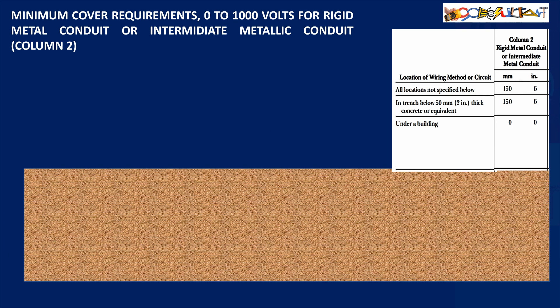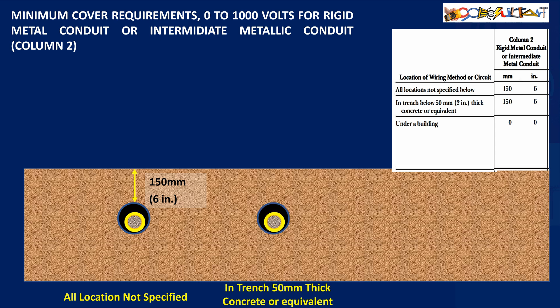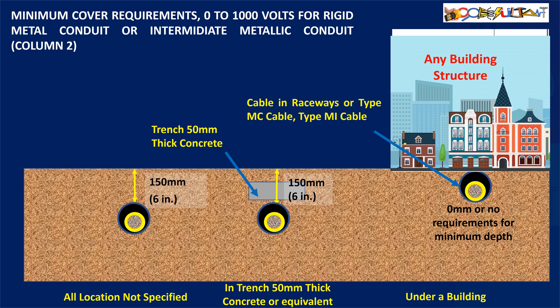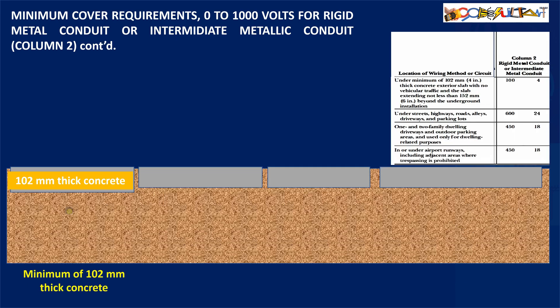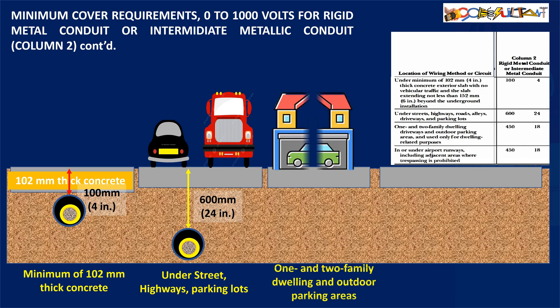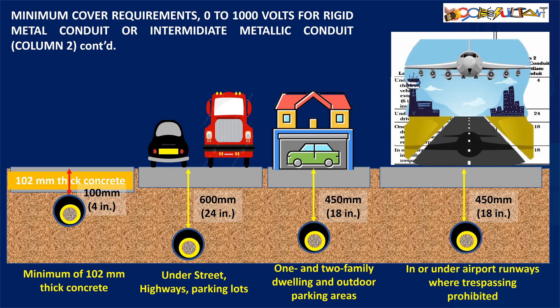For Column 2 (cables in rigid metallic conduit or intermediate metal conduit): in unspecified locations, the minimum cover depth is 150 mm (6 inches). This depth also applies if there is a trench cover of at least 50 mm (2 inches), or if installed under a building where there are no minimum cover depth requirements. In areas with concrete at least 102 mm (4 inches) thick and no vehicular traffic, the cover depth is 100 mm (4 inches). For installations under streets, highways, roads, alleys, driveways, or parking lots, the required cover depth is 600 mm (24 inches). For driveways and outdoor parking areas of one and two family dwellings, the cover depth is 450 mm (18 inches), the same as for airport runways.